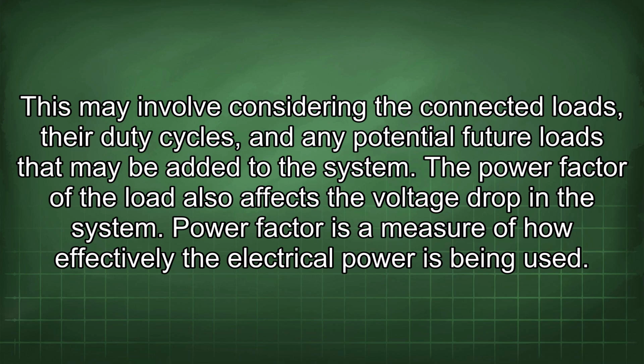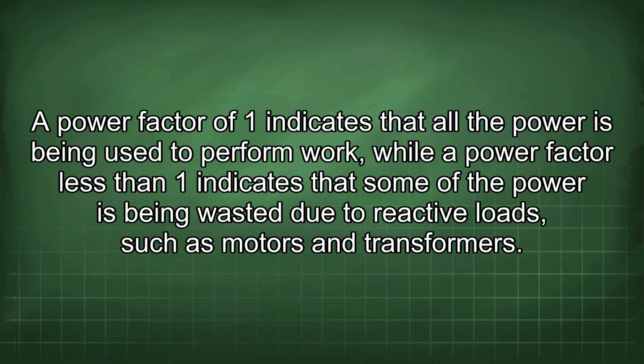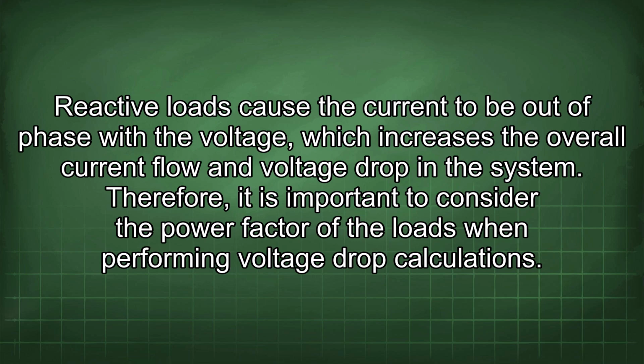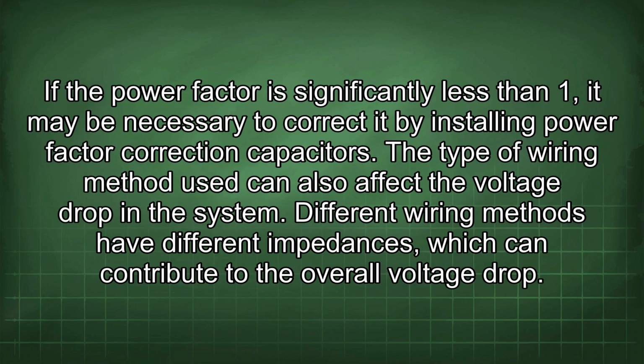Power factor is a measure of how effectively the electrical power is being used. A power factor of 1 indicates that all the power is being used to perform work, while a power factor less than 1 indicates that some of the power is being wasted due to reactive loads, such as motors and transformers. Reactive loads cause the current to be out of phase with the voltage, which increases the overall current flow and voltage drop in the system. Therefore, it is important to consider the power factor of the loads when performing voltage drop calculations. If the power factor is significantly less than 1, it may be necessary to correct it by installing power factor correction capacitors. The type of wiring method used can also affect the voltage drop in the system.